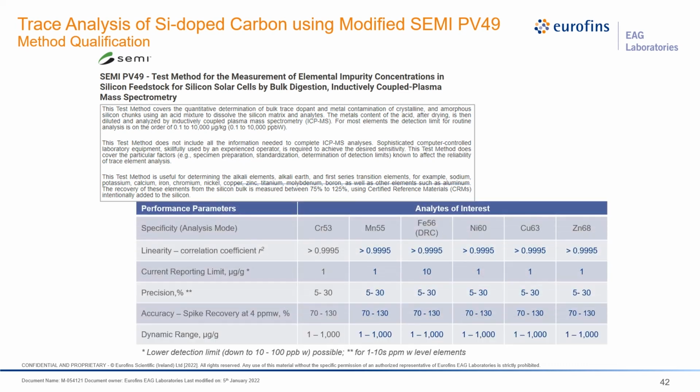So in EAG, we did our own method validations, and for those specific elements, we have done the linearity check, the detection limits determination, precision, accuracy, and dynamic range. Here it shows, and it gives very reasonable results that meet our performance acceptance criteria. With that, we have been using it to serve the industry.